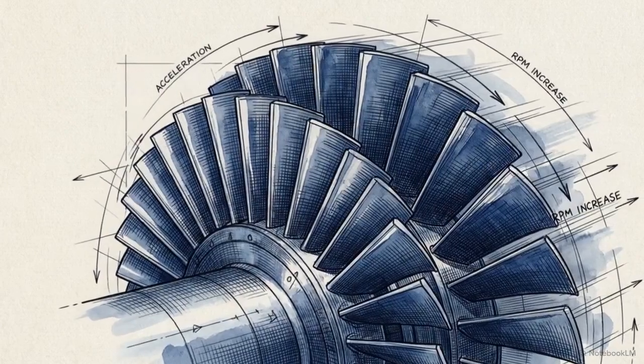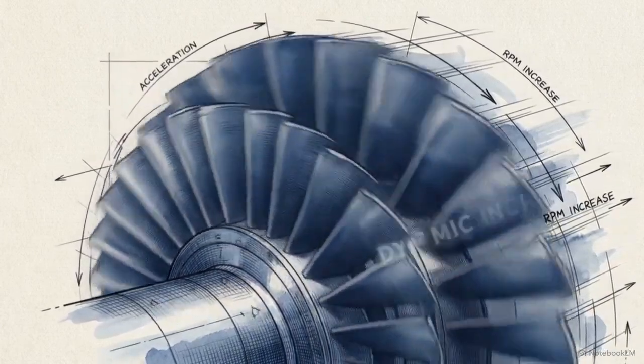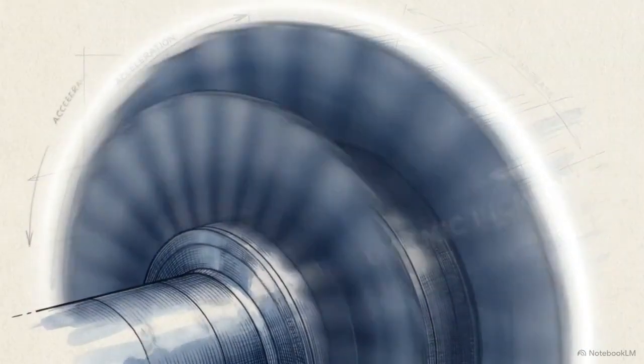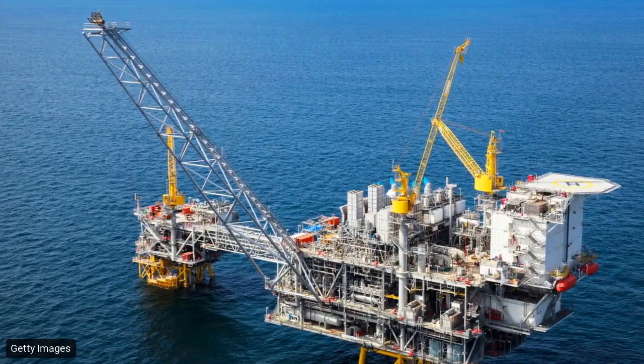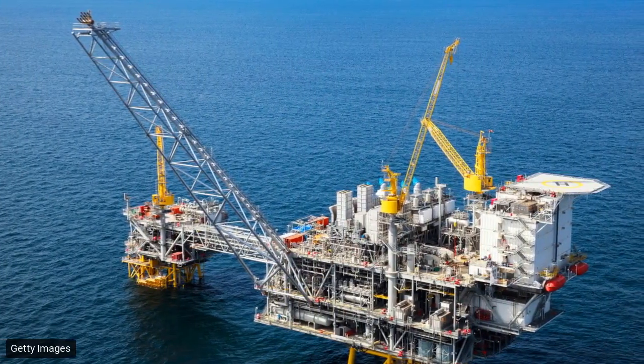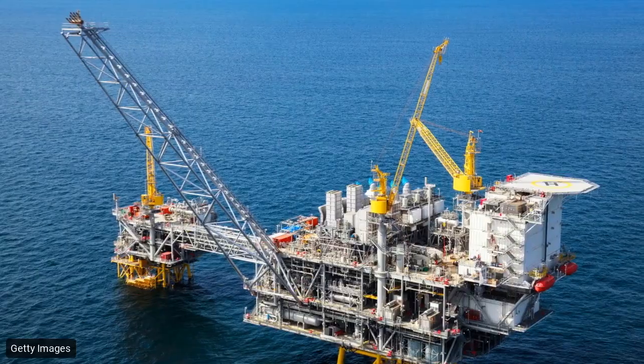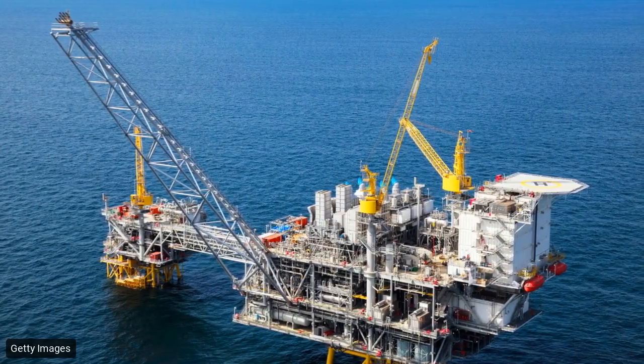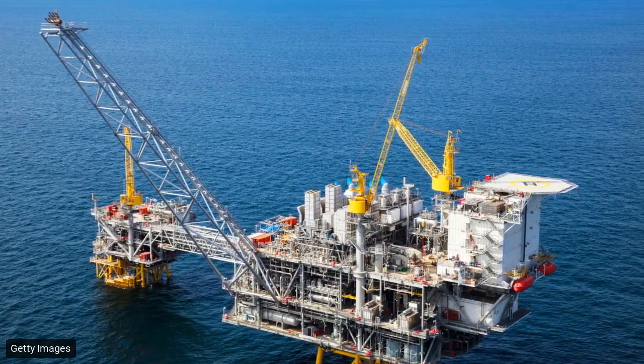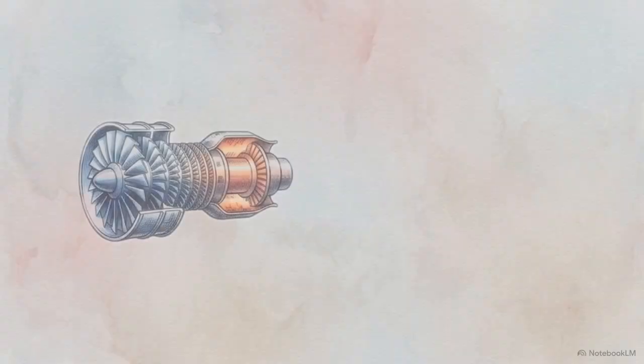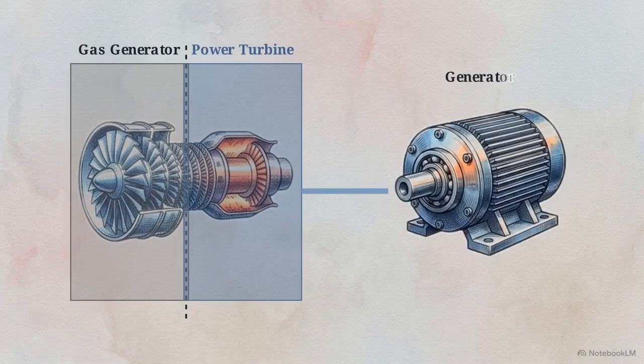Getting a massive aeroderivative turbine from a dead stop to a self-sustaining speed means pushing thousands of pounds of rotating metal past 10,000 RPM. These multi-million-dollar packages are purpose-built for the most demanding environments, delivering up to 60 megawatts of power to isolated offshore platforms and remote industrial sites. The power turbine section has one absolute requirement.